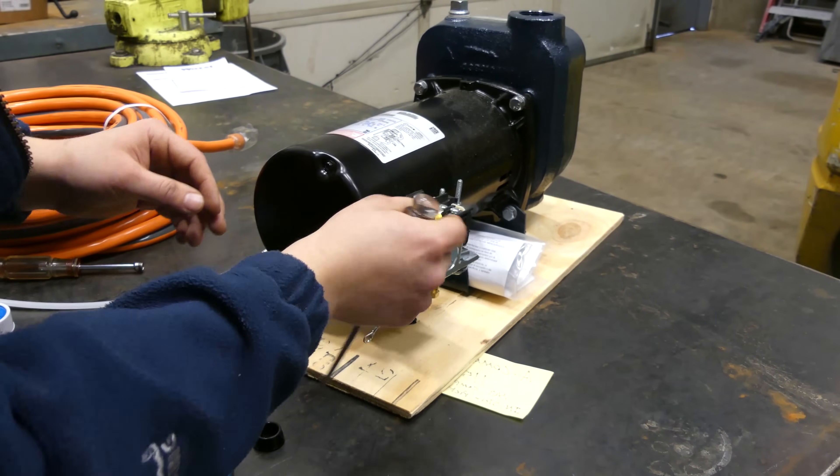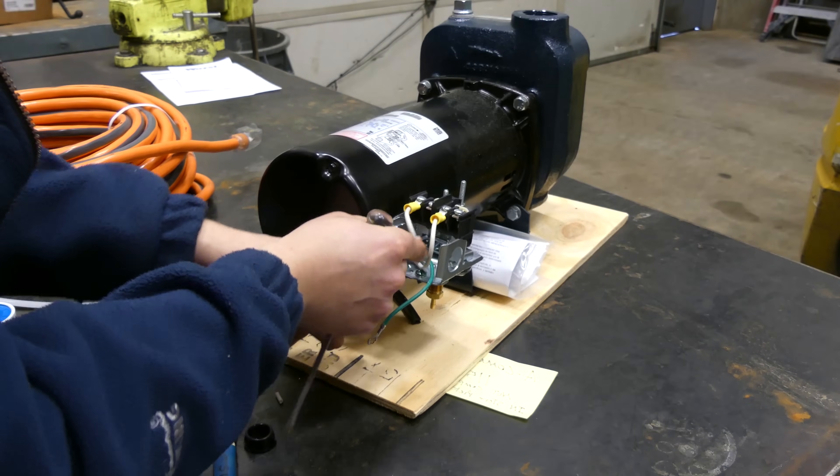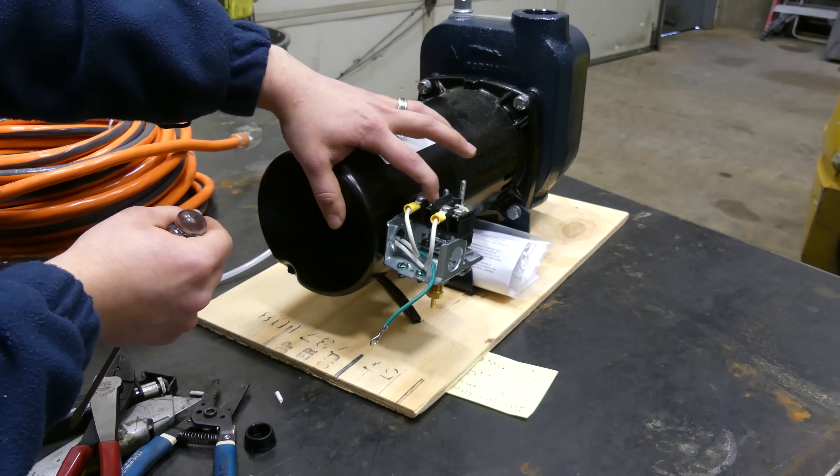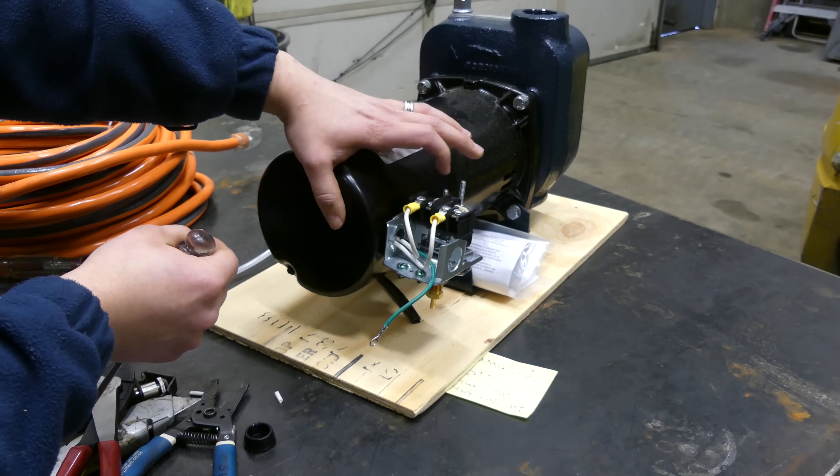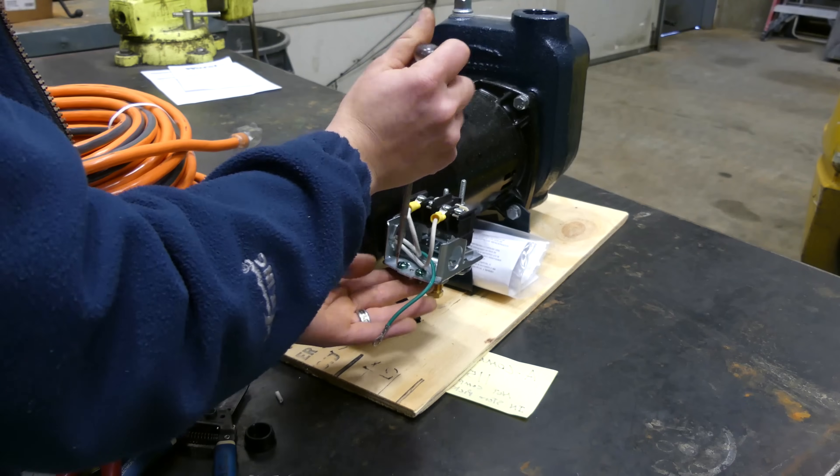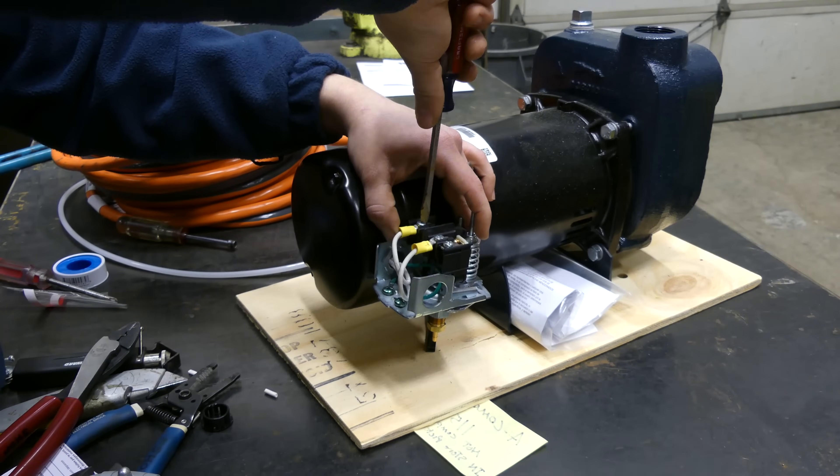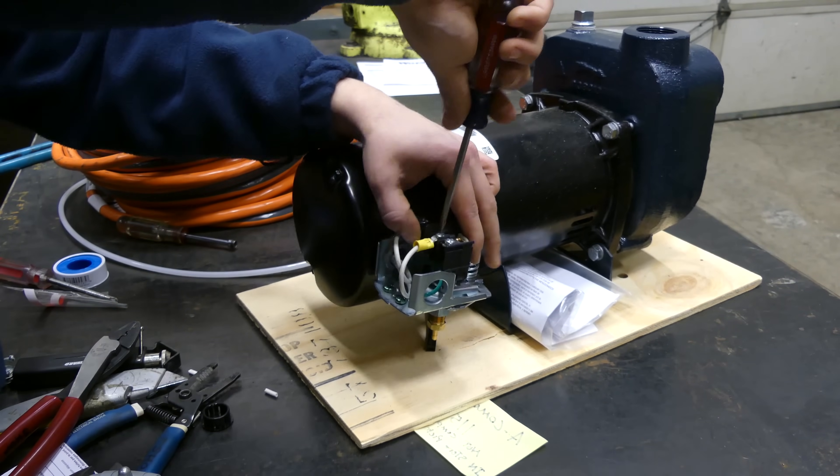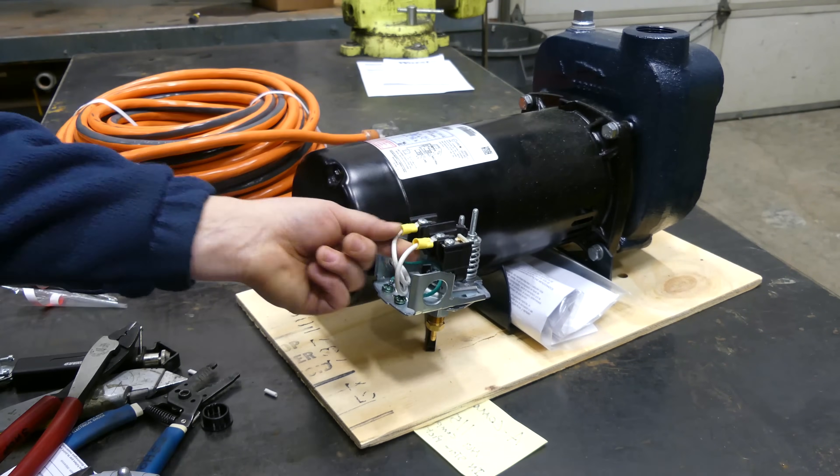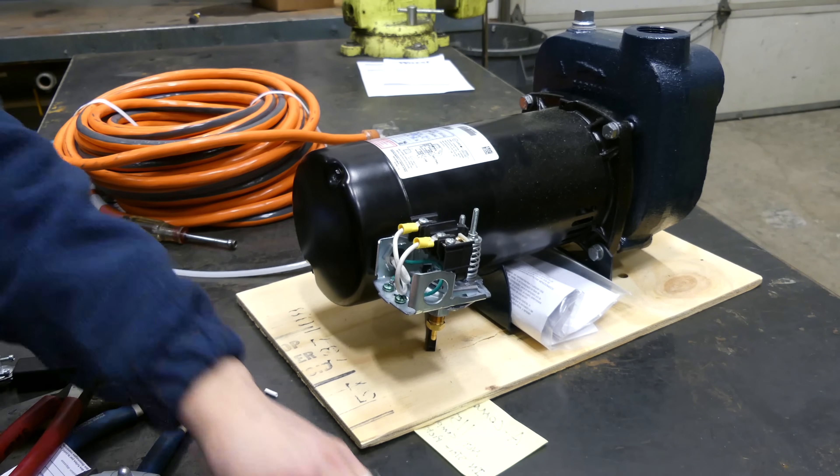So now we can just hook these up to our pressure switch. And we know that this here is our L1 because I marked it. So we're going to make sure that we put our L1 or our hot on the extension cord right here and then the neutral over here. And we're also going to have to hook up these grounds. And you want to make sure this is as tight as you can get it with your hand when you're working on pressure switches because the better connection, the better it's going to be.